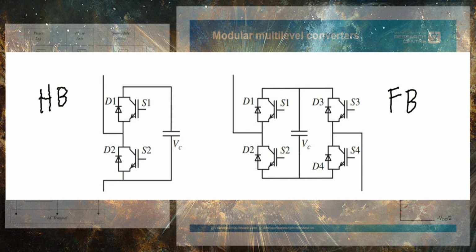not a primary concern. The full bridge cell contains four switches and a capacitor, allowing it to generate zero, positive, or negative voltage. This enables DC fault blocking capability, making full bridge cells suitable for HVDC systems where fault tolerance is critical. However, they require more components and lead to higher conduction losses compared to half bridge cells. The choice between half-bridge and full-bridge submodules depends on system requirements, such as fault tolerance, efficiency, and cost.